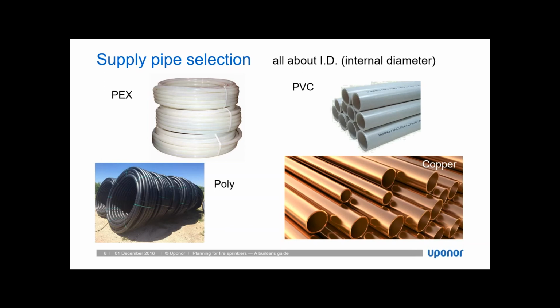One thing to note is even if you have a 3/4 inch meter, when you're talking to your water purveyor, they often call it a 3/4 inch tap. And that notation right there should throw up some red flags, because if they see 3/4 inch tap, that gives me the impression that they're planning on running 3/4 inch from the city main to the meter, and then they'll tell you that from that point on, you can increase and go the rest of the way into the home.